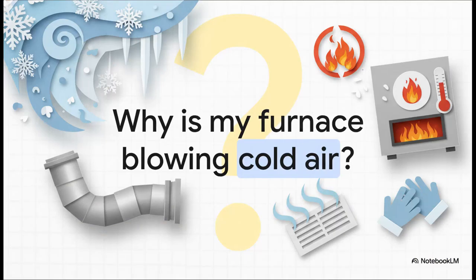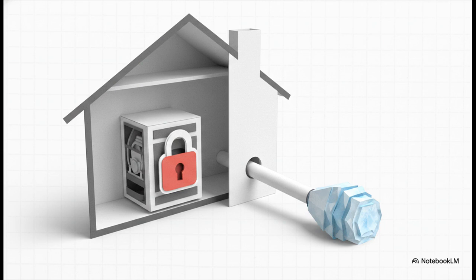This is one of the most common and, frankly, most infuriating calls a technician gets in the winter. You can feel the air coming out of the vents, but it's cold. You're paying for heat and getting the exact opposite. So what's going on here? A lot of the time, it's actually not some catastrophic disaster. These high-efficiency furnaces create water as a byproduct, and that water has to drain outside. When it gets really cold, that little drain line can freeze solid, and your system is actually smart enough to know this is a problem, so it shuts itself down for safety. Sometimes, the fix is as simple as carefully thawing that line out.